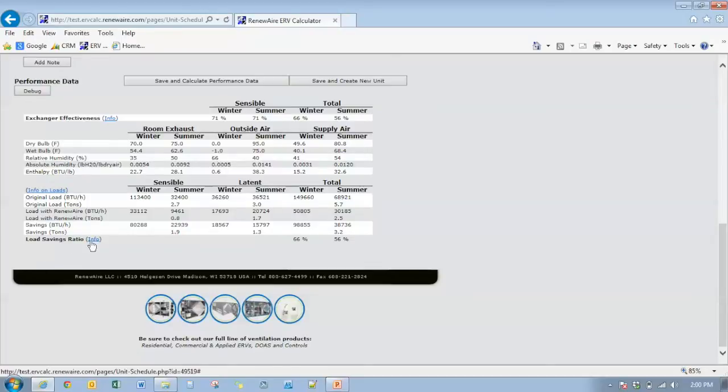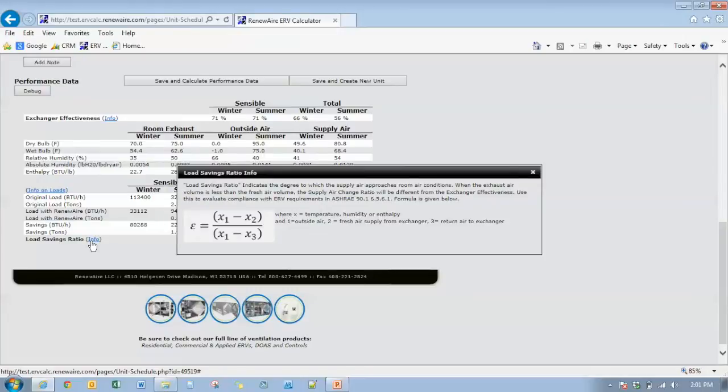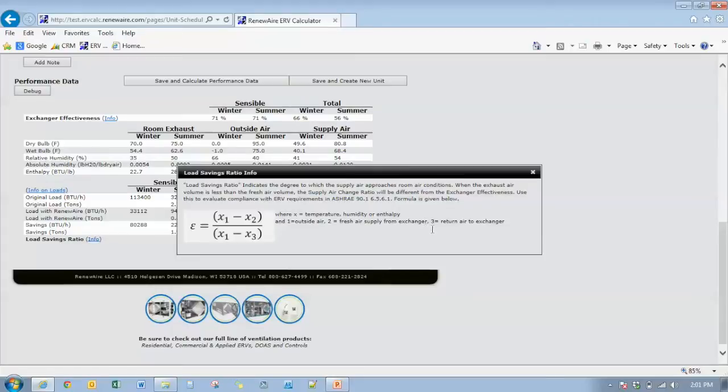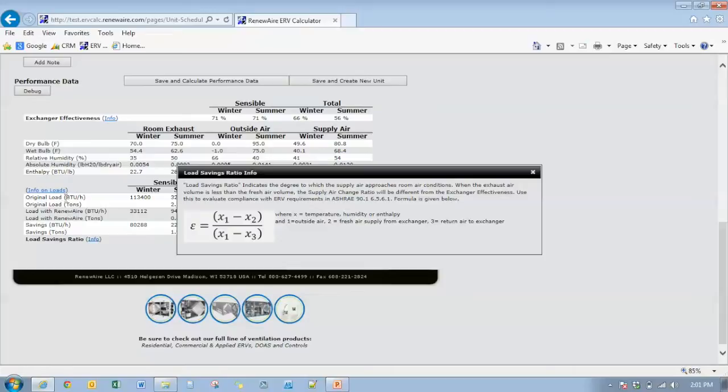We have load savings ratio down here. Load savings ratio is the calculation effectiveness as defined by 90.1. If you click on that, in the info button there, you'll see that the effectiveness is the effectiveness of the fresh air coming into the building. And that's the load reduction associated with the energy recovery device on the outside air that's being introduced to the building.